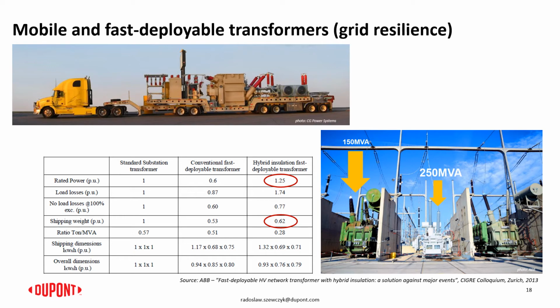So that was a spare unit to be installed in some critical locations in the grid to avoid keeping spare transformers in every single substation throughout the state. And this transformer required disassembling for the transportation because it could not be transported with the 400 kilovolt bushings. After draining the oil and dismantling the bushings for the transportation, the size and weight were significantly smaller than conventional transformers. And we can see the comparison of this new 250 MVA unit as compared to the older 150 MVA units, which were much bigger and much more difficult for the transportation.